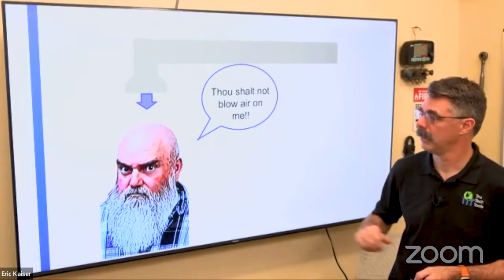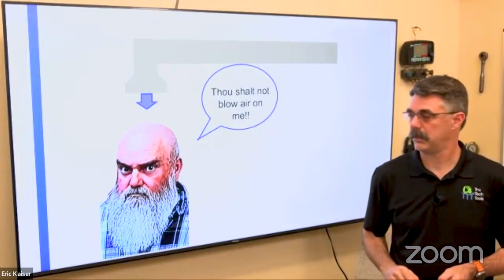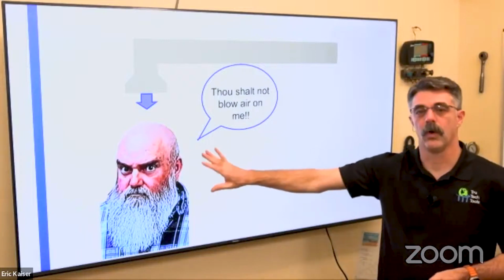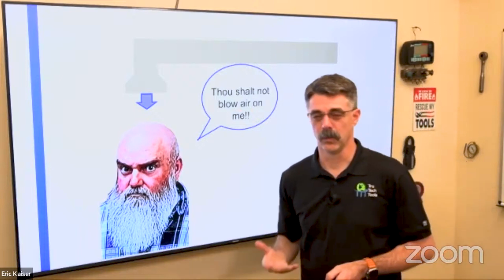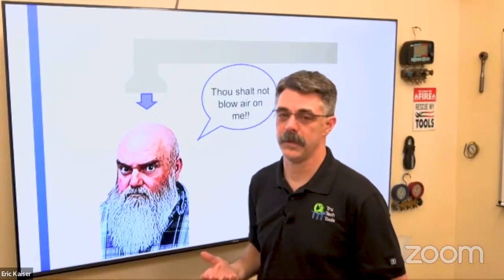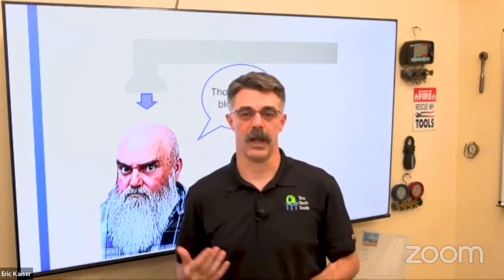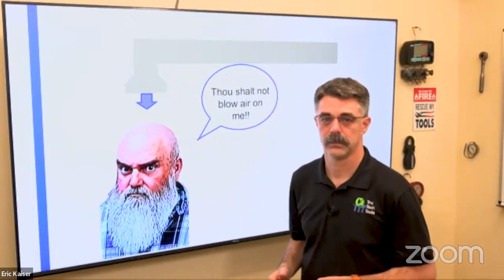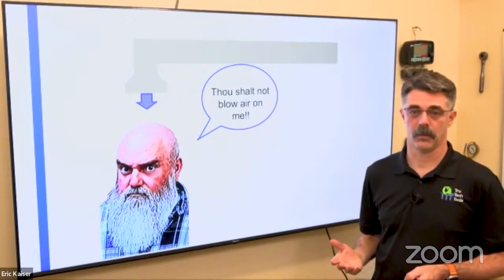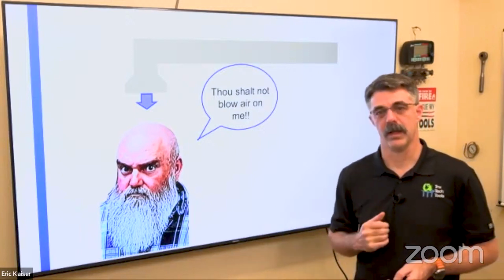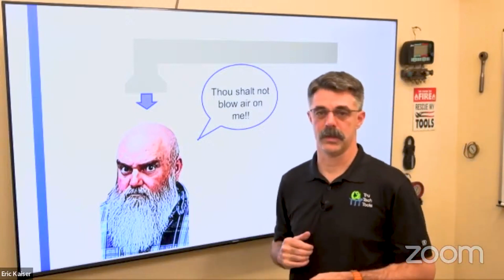Okay. As Mr. Angry Ed says here, don't blow air on people. The rule is less than 50 FPM hitting a person, and they typically won't feel it. Now, some people may be a little bit more sensitive to that, but again, that's all going to be part of your Manual T process.